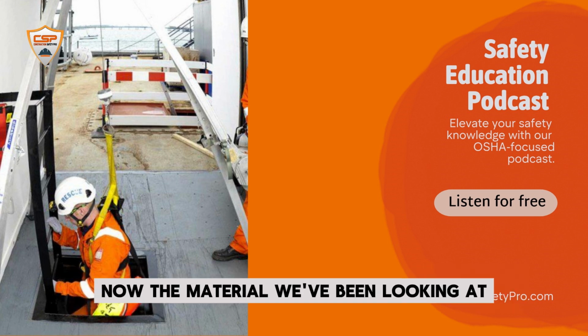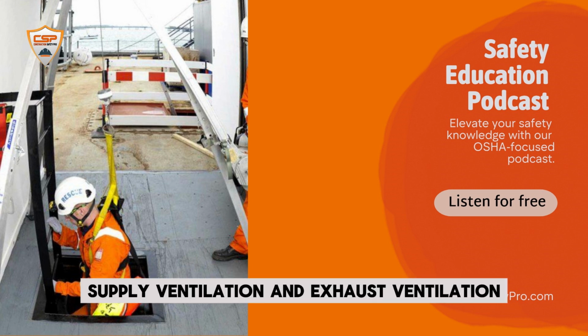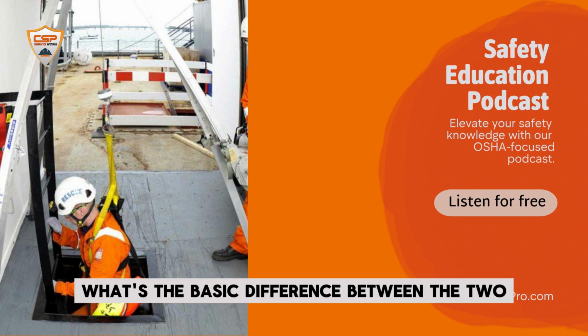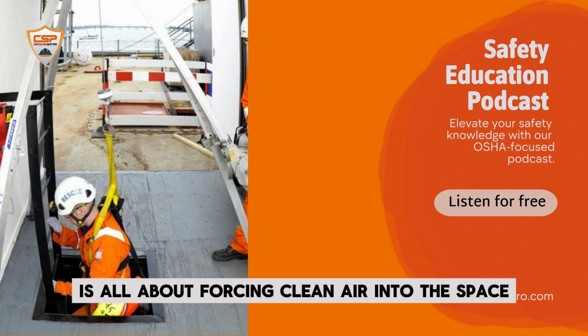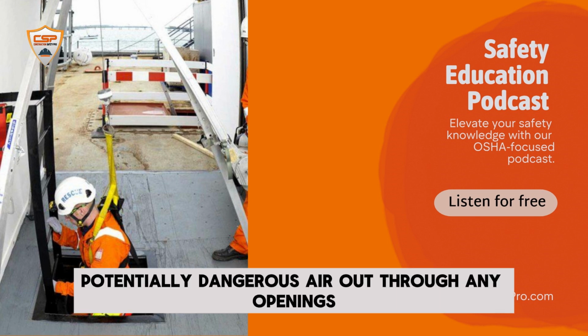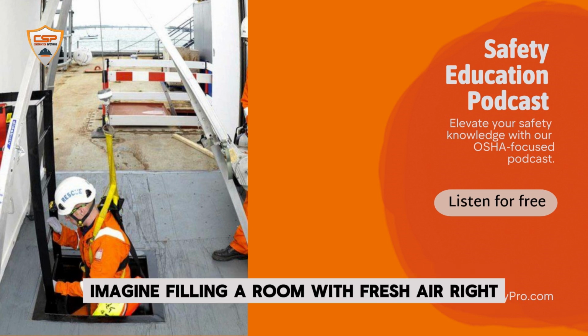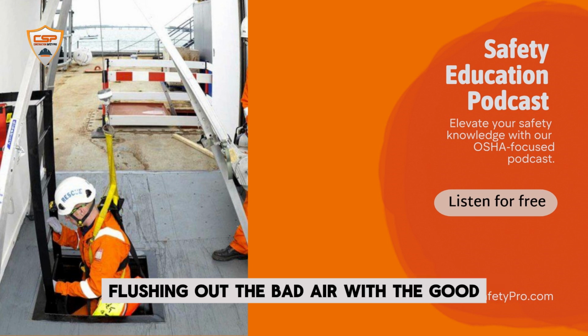Now, the material we've been looking at talks about two main approaches: supply ventilation and exhaust ventilation. What's the basic difference between the two? Sure. Supply ventilation, as the name suggests, is all about forcing clean air into the space. This creates what we call positive pressure, which pushes the old, potentially dangerous air out through any openings or through exhaust points. Imagine filling a room with fresh air, right? The stale air has to go somewhere. So you're essentially flushing out the bad air with the good.